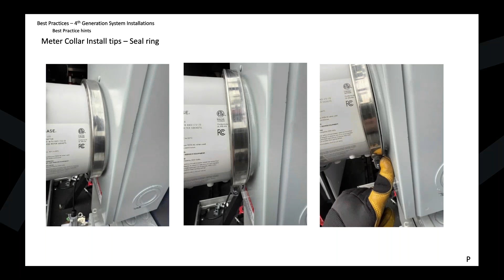Next thing here is talk a little bit about the orientation of the actual meter collar. So there's specific right and wrong way to install it. We want to make sure that when it's installed, we have the up arrow, so you can see the little red box around the meter collar there. It's kind of hard to see, but when you have it in your hand, it's clear. But that's actually going to be up for a reason. So that's going to identify when it's installed into a separate meter pan, or into the pan where the utility meter is going to be on top of it.